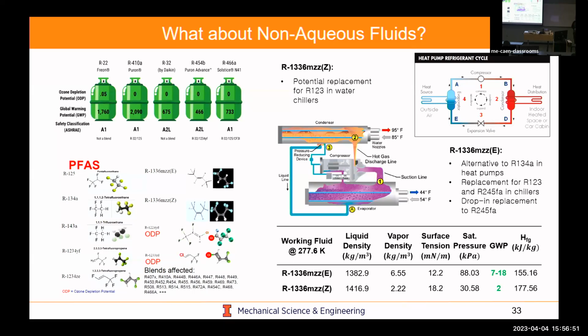The nice thing about the MZZE and Z is they're known as low pressure refrigerants—they typically operate at 1 to 2 bar, while R134A operates between 5 to 7 bar. If you use that as a leak proxy, the leak rate would be smaller, but I haven't heard an argument made for that. I think you just have to assume the leak rate will still be high.